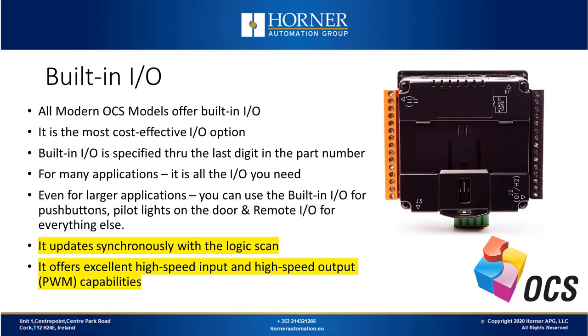You order it with the IO complement that you want. In many applications, especially smaller ones, the built-in IO could be all the IO you need. Even in larger applications, you can use the built-in IO for push buttons and pilot lights on the door, and remote IO for everything else. Built-in IO updates synchronously with the logic scan, whereas remote IO is asynchronous. The built-in IO offers excellent high-speed counter capability and high-speed output capability.